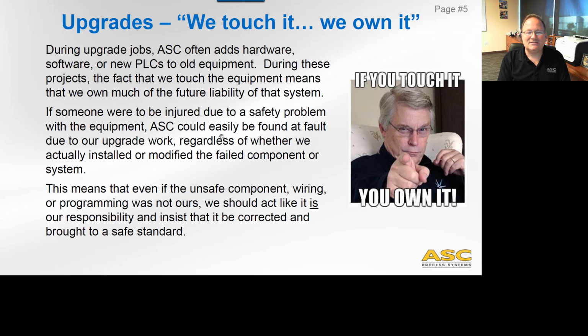component or system. And that's an important thing, is if we're going in and working on one part of the equipment and the other part of the equipment has a safety issue and fails, then we can easily be found at fault because we're the experts and we should have known that and we should have addressed it. And so what it means is that even if the unsafe component, wiring, or programming was not ours to begin with, the fact that we're there and we see it, we should act like it is our responsibility and insist that it be corrected and brought to a safe standard.